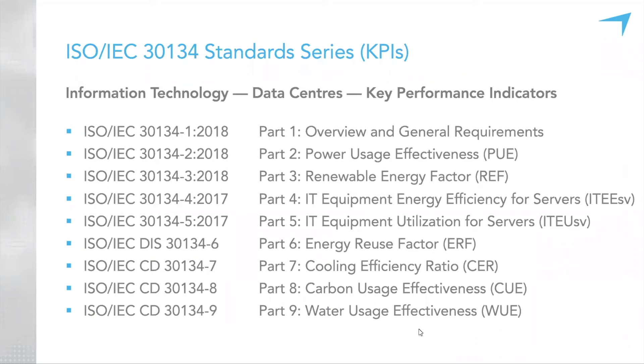We've also got a metric on Renewable Energy Factor (REF) — the amount of renewable energy actually being used on site. Then there are additional metrics people are less familiar with: energy efficiency metrics for servers defined within this series, and equipment utilization levels for servers. It's important to measure not just server energy efficiency but also how much those servers are being utilized — typically across a data center estate we see fairly low utilization, possibly up to 20–40% at maximum, even with virtualization.